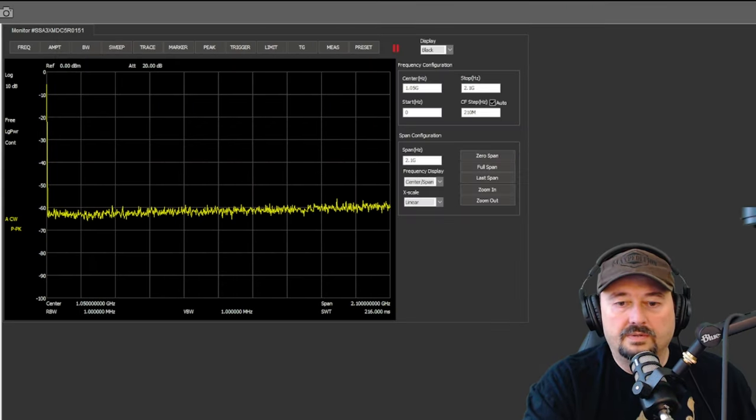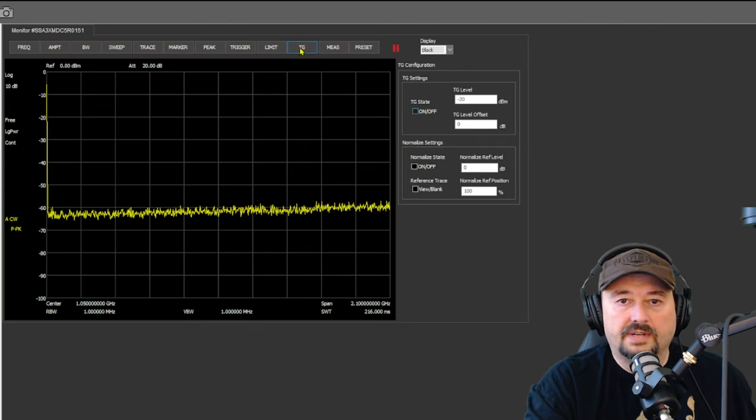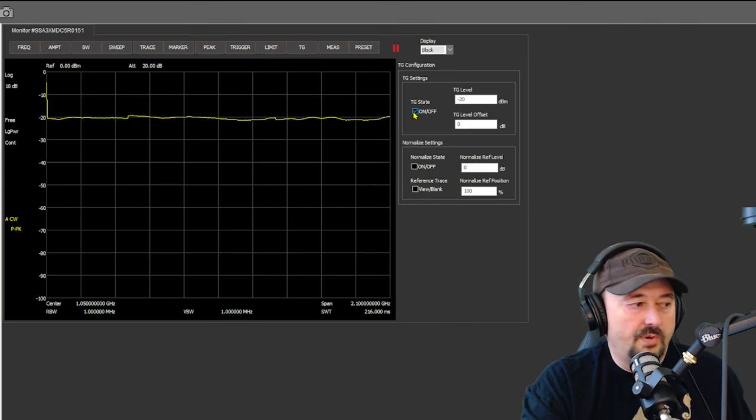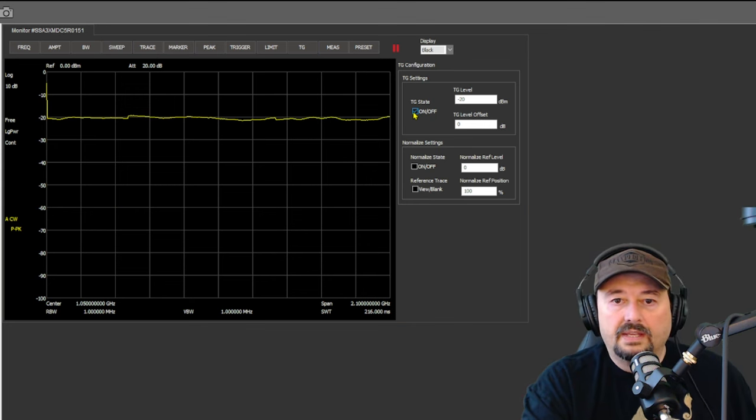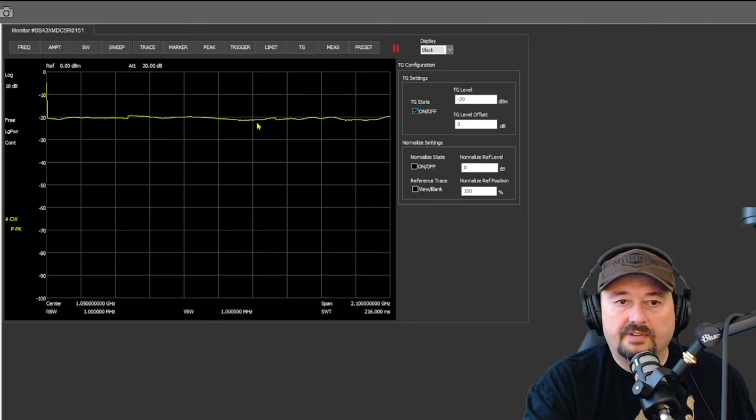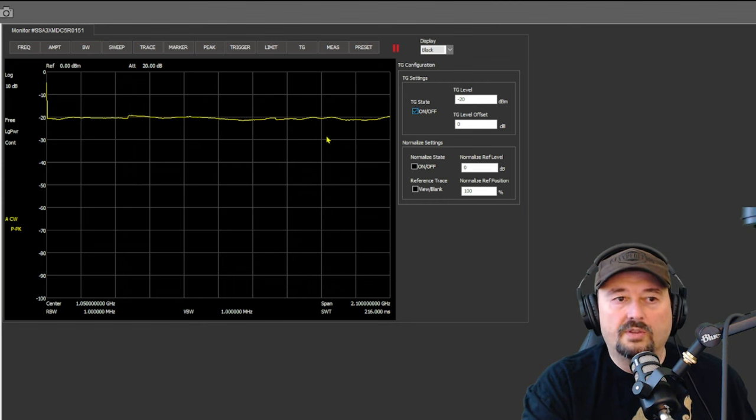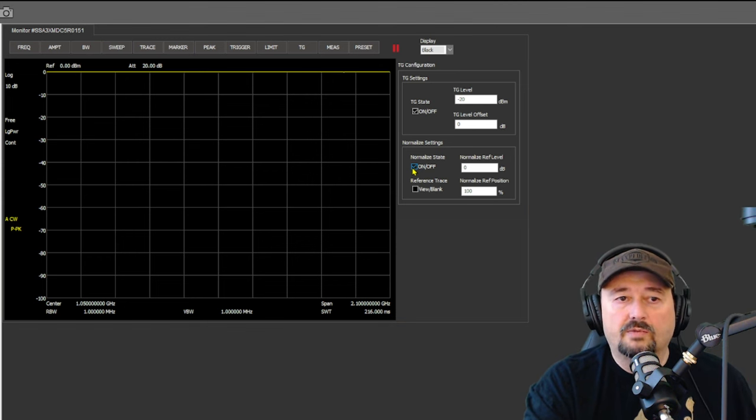So what I want to do is I'm going to turn on the tracking generator. And I do that like this. Tracking generator state on. And what that's doing is feeding the signal out my tracking generator port and into my RF input. Now, what I want to do is normalize this because you can see that we do have some variation in here. And that is a result of the cables and the connector that we're using. So by normalizing that, I basically null that out. So let me go ahead and do that. And now what you see is we have a flat line across the top. And we're ready to connect our attenuator in series with our lead cables.